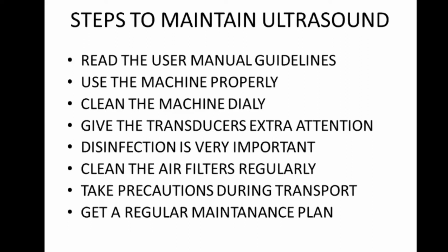Then, take precautions during transport. If you are taking the machine in ambulatory service, or transporting it from one place to another, or taking it to any hospital for emergency cases, you should transport it properly. If you fail to do that, the first thing that gets affected in the ultrasound is the monitor, the entire monitor can collapse, and if you turn on the system, it won't turn on. Sometimes we have faced these issues while giving demos.